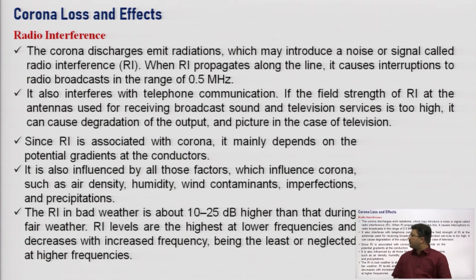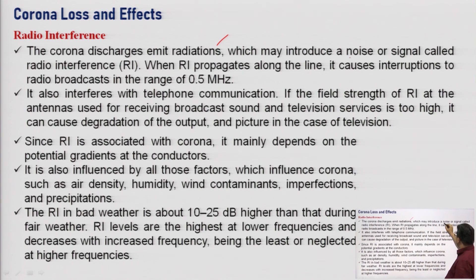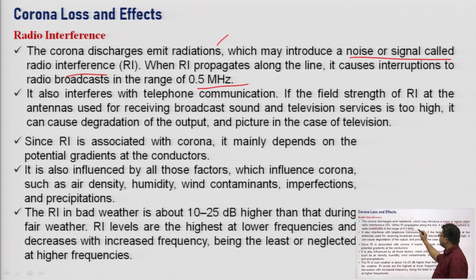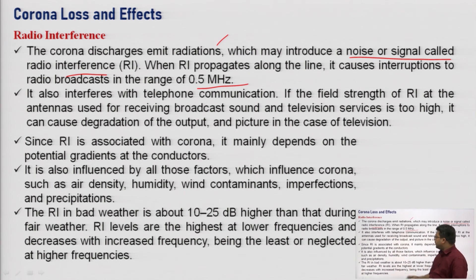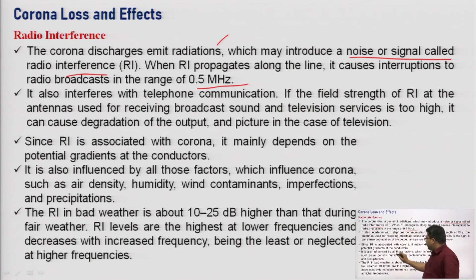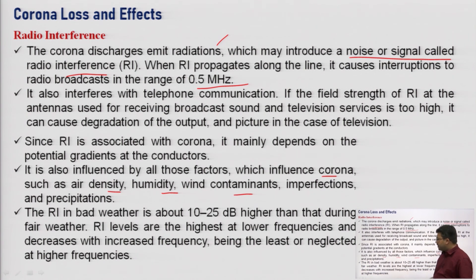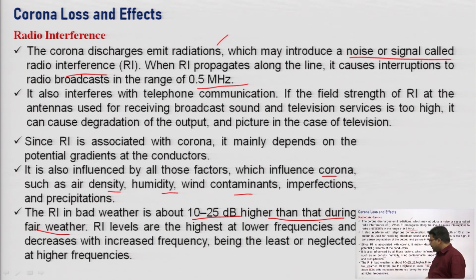Another impact is radio interference: corona discharge emits radiation which introduces noise in signals — this is called radio interference, up to a range of 0.5 MHz. It interferes with telephone communication and radio signals. Factors such as air density, humidity, and wind affect this interference. During bad weather, radio interference can be 10 to 25 dB higher than during fair weather.